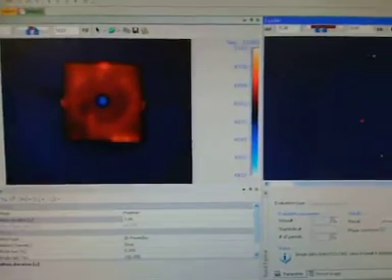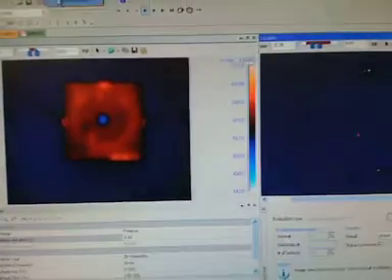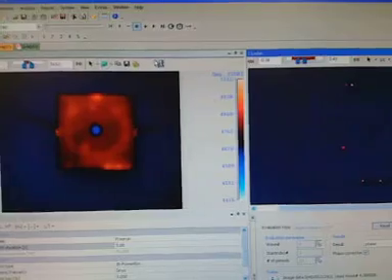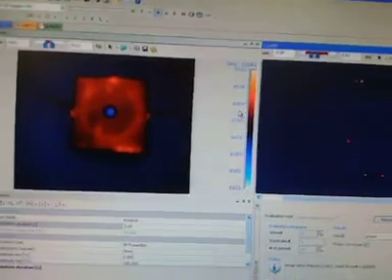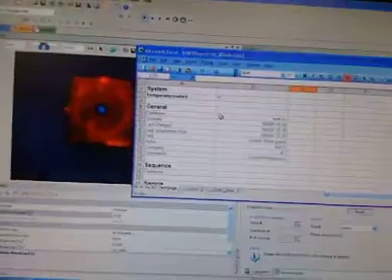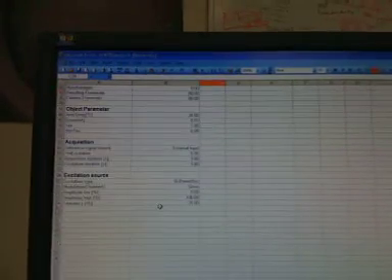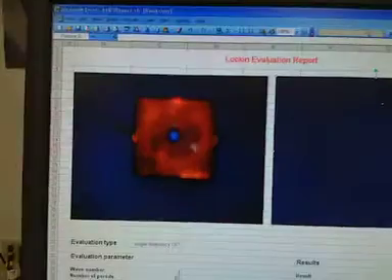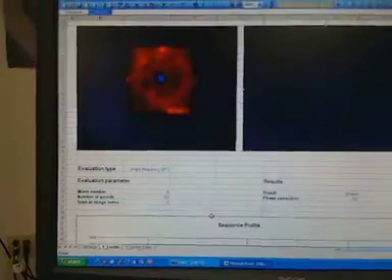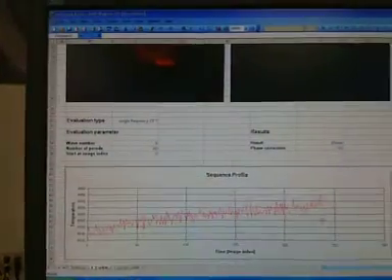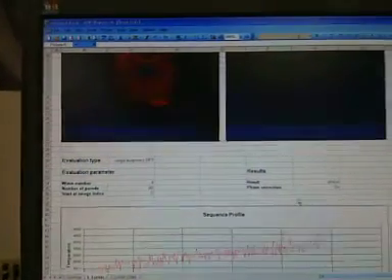We also have a quick way to generate reports based on our results and it records all of the settings and the results as well as a couple of pictures in Excel format. So it gives all of your test information here. The live image versus the results image. The sequence profile for a given region of interest. And it also gives you the lock-in data in column format if you want to do other analysis on it.